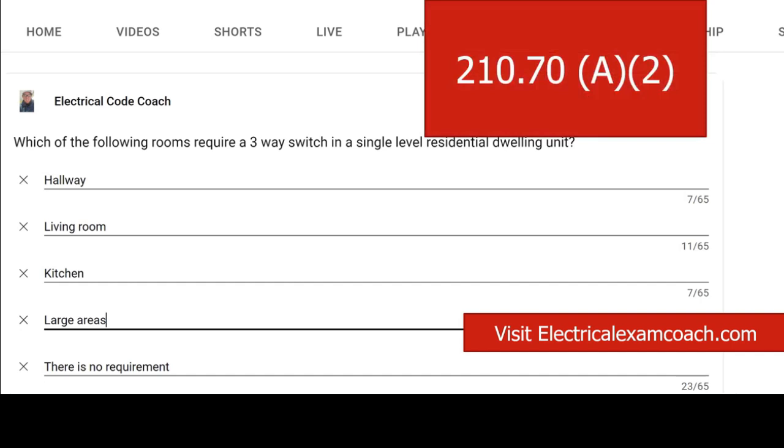What it states is that the only place in a residential setting where you're required to have a three-way switch at all is if you're dealing with a set of stairs and it has more than six risers. In that case, you'd have to have one at the bottom and at the top.